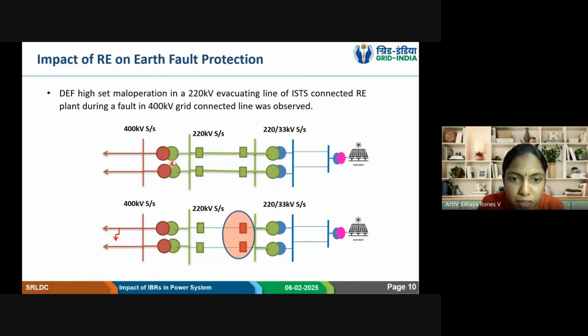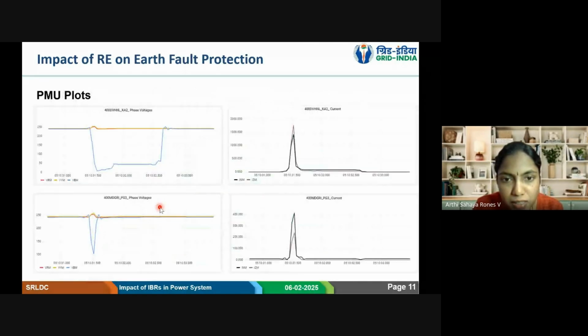And then here we are having the grid station. So this is called the POI. This is a grid point, and this 220 kV, this is called POI. So now the point is, the fault is after the POI, that is, it is a grid fault. During this time, from the grid end, from here, there will be a fault feeding to this particular thing. And from RE end also, some current will come from here. So the current that comes from the RE end, it is kind of a zero sequence current. So it will be like this.